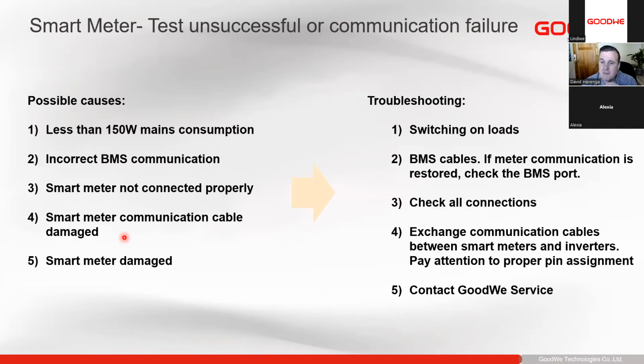If you replace the smart meter cable because the customer's utility box is further than 15 meters from the inverter, replace the entire cable. It's normally just a few screws under the inverter, 4 little screws. You open the cover, put in a new cable, crimp an RJ45, and run the whole new cable all the way. So please don't use an extender or anything like that because it does cause extra interference. And lastly, there's always a possibility that the smart meter is damaged. Very seldom do we get smart meters that are faulty. More often than not, 99% of the time, it is a wiring mistake or something like that.